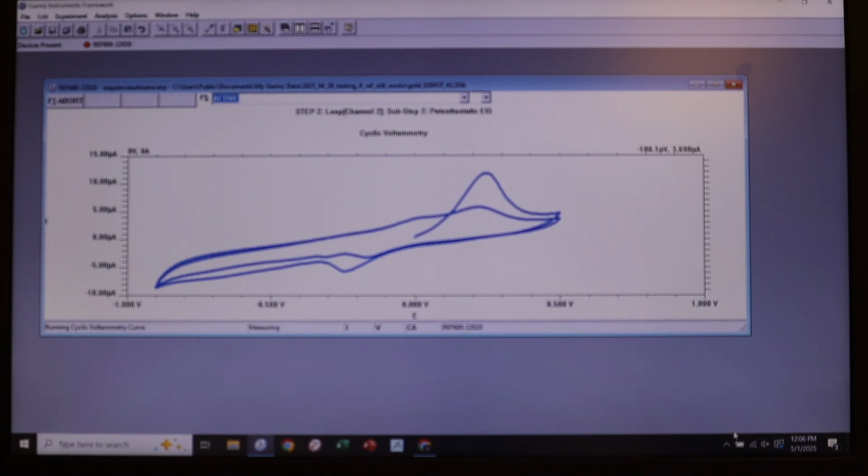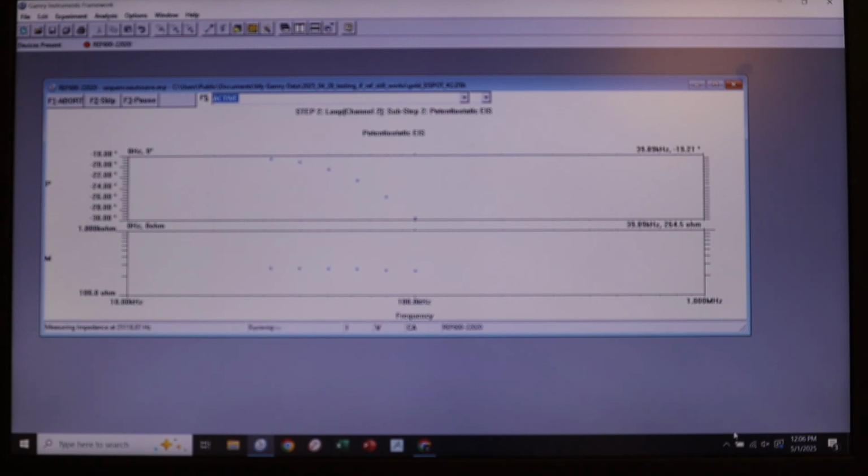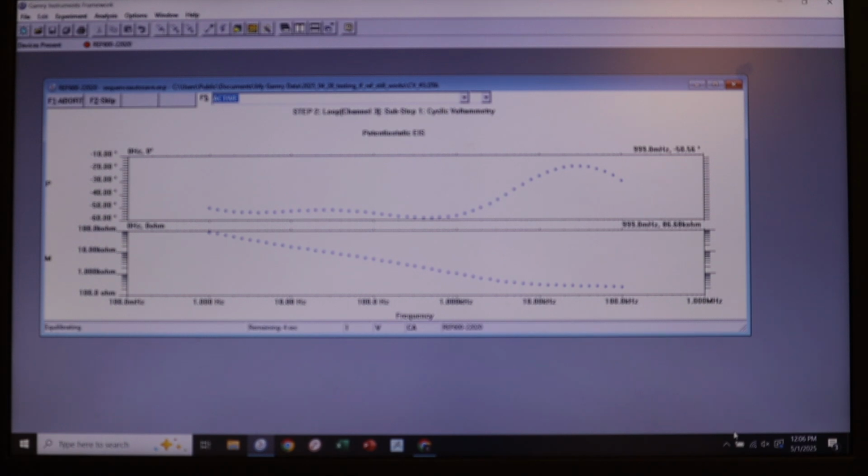So it's not always inherently apparent what is going wrong with the Gamry or with your electrochemistry when you show up one day and things are going awry. But it's always important to kind of follow these general troubleshooting steps if problems do occur. So of course making sure that all of the connections are made, your working electrode is functioning and is actually able to show electrochemical values.